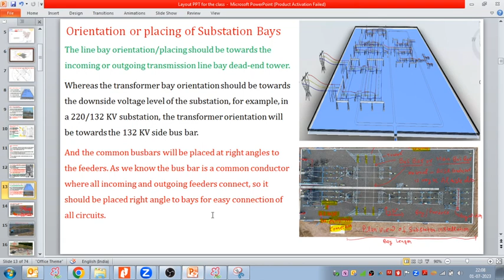If you focus on my cursor, this is the line bay, and we took the 90-degree angle coming here, and this direction is my bus bar bay. Coming here you can see these three conductors are the common bus bar. Here we have the towers, and these three conductors are the main bus bar. The material could be ACSR conductor or aluminum tube. If we place it at 90 degrees, this can be connected here and this can be connected here. Due to that we place it at a 90-degree angle.